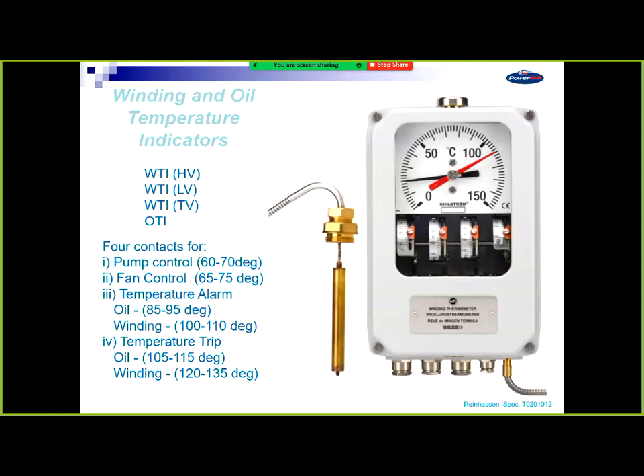If it gets too hot again, we then trip the transformer. And the way we do it in PowerLink is we don't trip the transformer like a protection trip, which is tripping the HV and LV breaker. We know that temperature is an overload condition. So what we do is just trip the low voltage circuit breaker to drop the load off. That keeps the transformer energised so the operators know there's nothing wrong with the transformer, it's just hot. So you need to take some other action to drop the load off, but you can put the transformer back in service whenever you want to. You don't need to send people to the field, or you make a choice on that.